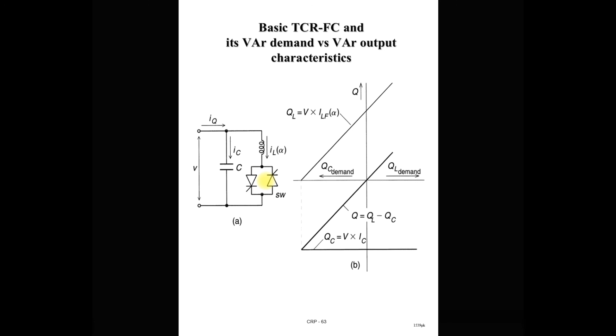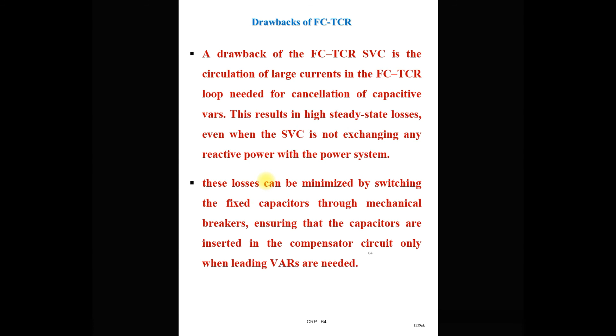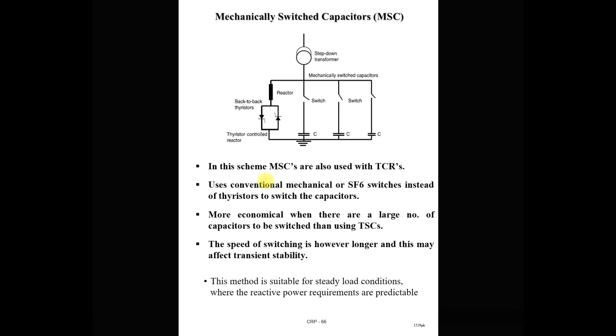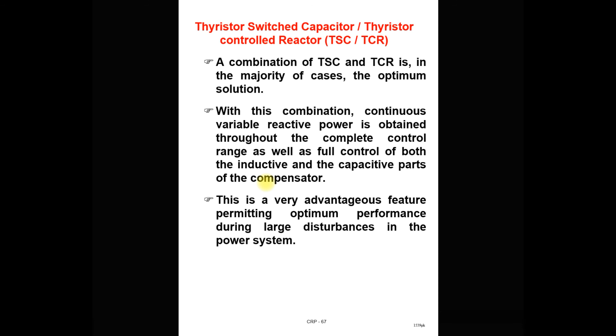So that's why the thyristor switched capacitor is very important for the dynamic compensation of the power system and reduces the losses in the system. So that's why generally we use the thyristor switched capacitor, or mechanically switched capacitor, with thyristor controlled reactor, or thyristor switched capacitor, thyristor controlled reactor, for the optimum solution of the power system for the dynamic compensation of the power system.